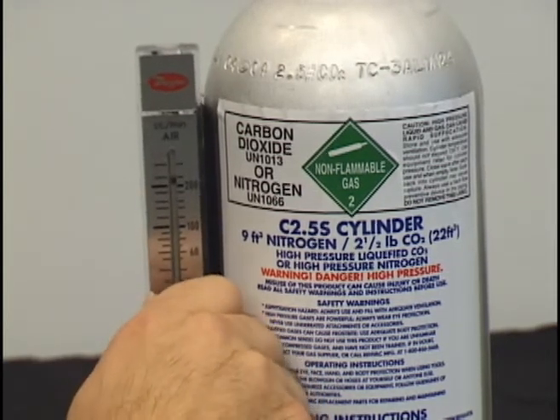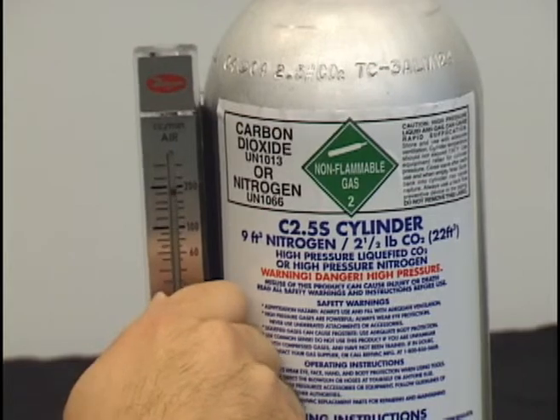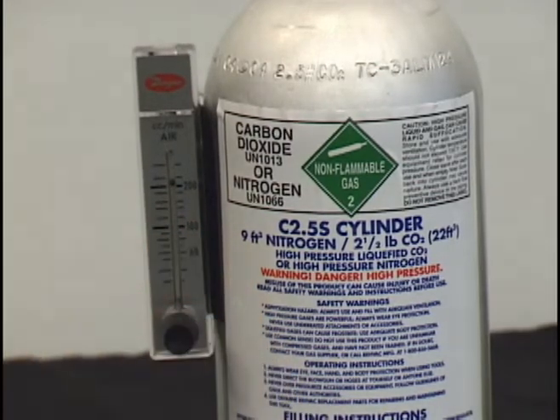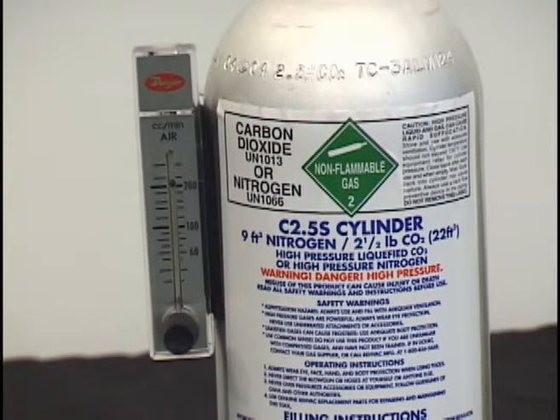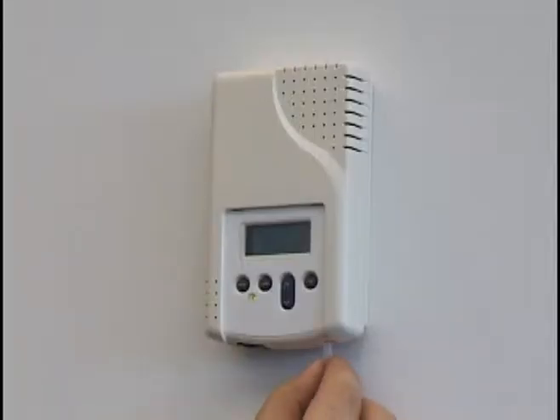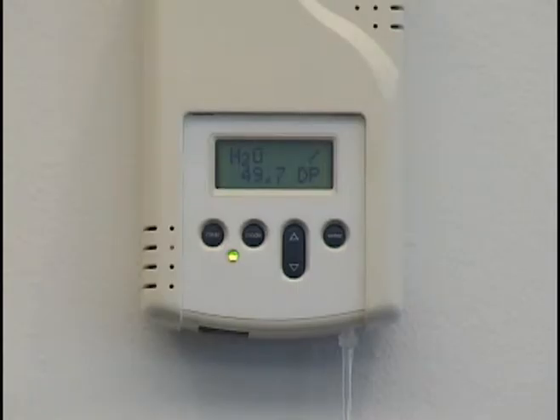Some small fluctuation in flow rate is acceptable. However, the flow rate should always stay above 150 cc's per minute for the entire calibration process. Connect the 1/8-inch Tygon tubing to the sensor's calibration port. View the VaporStat. Verify that the reading starts to drop. If it does not drop, check your gas flow and tubing connections.